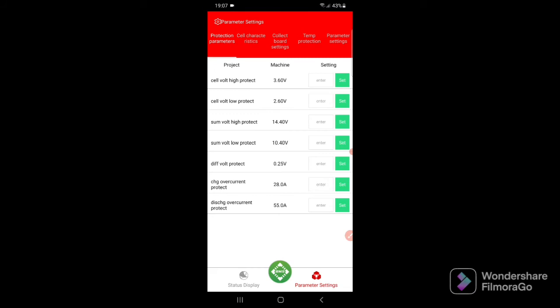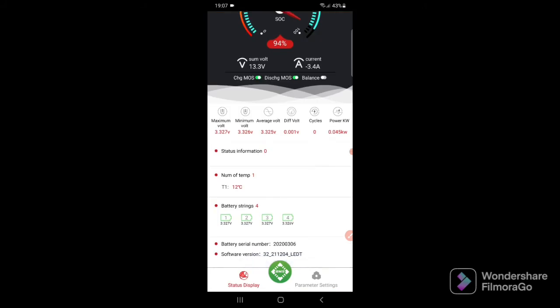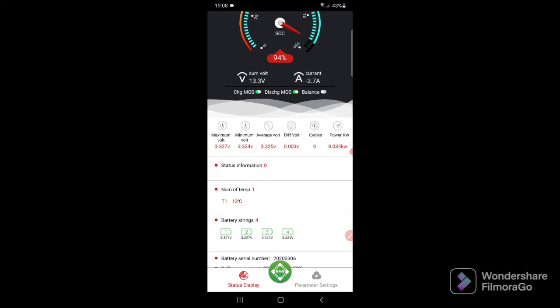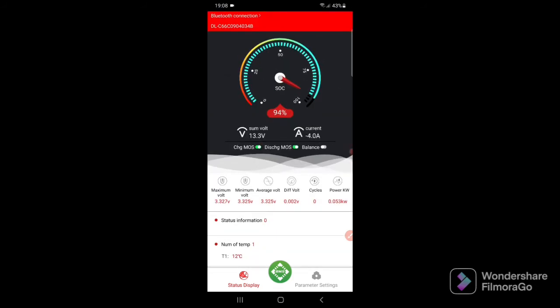If we go back to this screen, I've got the cell volt high protect set at 3.6, so that's the maximum it can get to. Balance open start volt means once it gets to 3.45 volts, it will try to start balancing. The balancing process is this diff voltage we talked about. Once it gets above 3.45 volts per cell, it will start trying to balance all the cells, and you'll see the little balance icon come on at the top, telling you it is balancing.